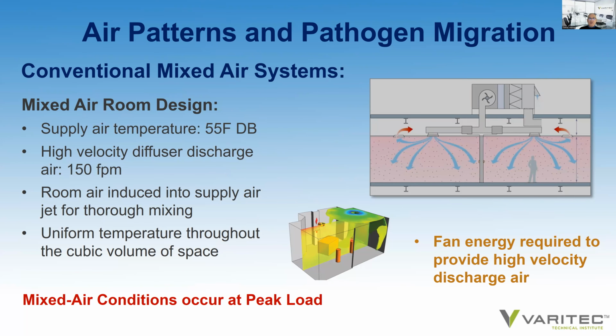So let's quickly review a conventional HVAC design to promote and create a mixed air environment. From previous sessions, maybe you'll recall that supply air is injected at high velocity at 55 degrees. And you should see a terminal velocity out of the diffuser of 150 feet per minute, so air can achieve Coanda along the surface to which it's supplied across, inducing room air into the jet that allows for proper mixing of the air in the room. So room air is induced into the jet, and by this general mixed air supply strategy, a mixed air environment is created where you have a uniformity of temperature throughout the cubic volume of space of plus or minus 2 degrees to meet ASHRAE standard 55.